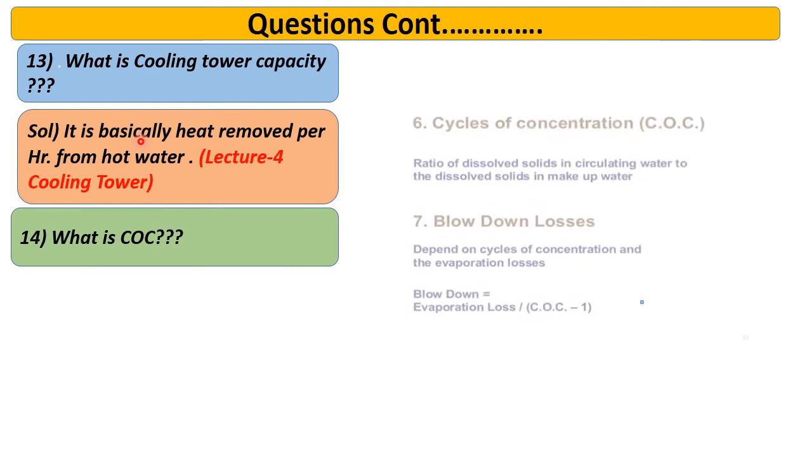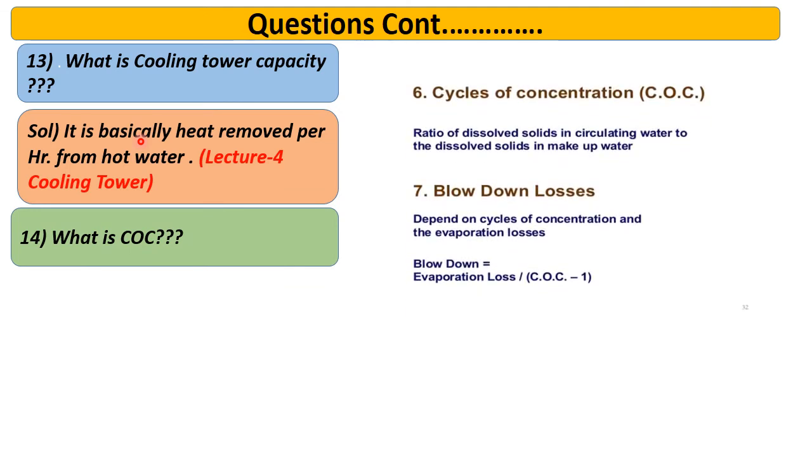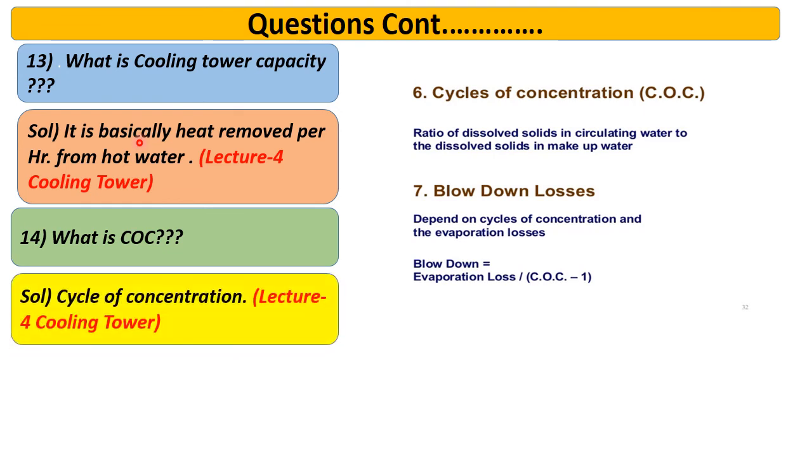What is COC? Friends, COC is basically the cycle of concentration. Here you can see that it is the ratio of dissolved solids in the circulating water with respect to the dissolved solids in the makeup water. So friends, that is basically the COC, the cycle of concentration. I have covered this in a very detailed way in my lecture 4 of cooling tower.